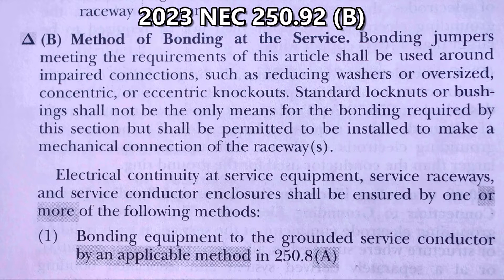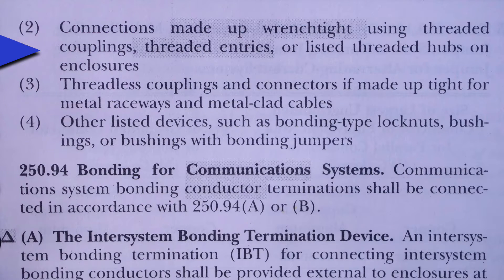Electrical continuity at service equipment, service raceways, and service conductor enclosures shall be ensured by one or more of the following methods: one, bonding equipment to the grounded service conductor by an applicable method in 250.8(a); two, connections made up wrench tight using threaded couplings, threaded entries, or listed threaded hubs on enclosures; three, threadless couplings and connectors if made up tight for metal raceways and metal clad cables.